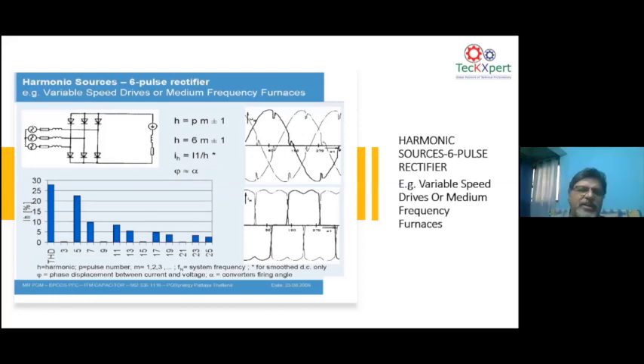Also, of course, there are active front-end drives. But I just want to warn you about them. First, what is a VFD? A VFD takes an AC input and converts it to DC by a rectifier. Then that DC is converted to AC by an inverter, and the inverter generates the required voltage and frequency so that the connected motor will run at the required speed. That is how a conventional AC drive works.